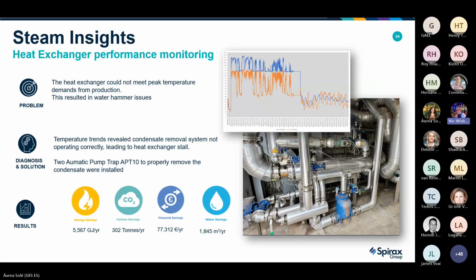So steam insights, heat exchanger performance. As we were talking, if you monitor your steam heat exchanger, there is a point on most heat exchangers, unless they're very well installed, where they reach stall. What we mean by stall is, if you have a control valve before a heat exchanger to control the flow of steam into it, to control the heat, at some point that will close. When that closes, the steam downstream from there collapses and pulls a vacuum. That allows water to build up in the heat exchanger, which means that you then get less efficient heat systems.